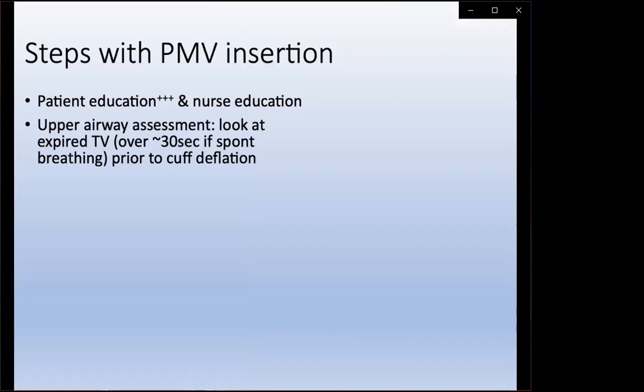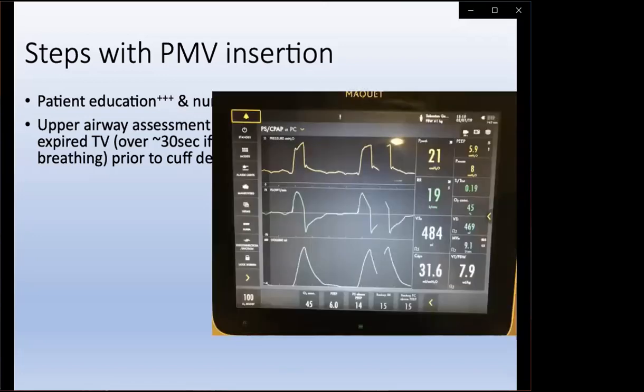Then moving on to upper airway assessment, so looking at expired tidal volumes prior to cuff deflation. If the patient is not on full mandatory ventilation and is initiating their own breaths, therefore deciding the size of the breath themselves, then it's necessary to look at that expired tidal volume over 30 seconds or so to get the average tidal volume. I've just used a Maquet overview screen here as an example of where those expired tidal volumes sit. Obviously different ventilators will have them in a different place, so get to know your ventilator and see where the values are that you need to monitor.